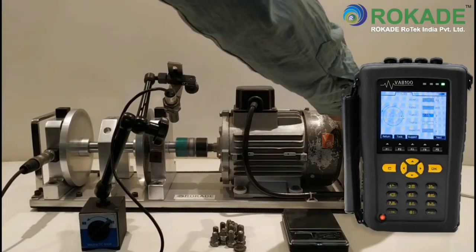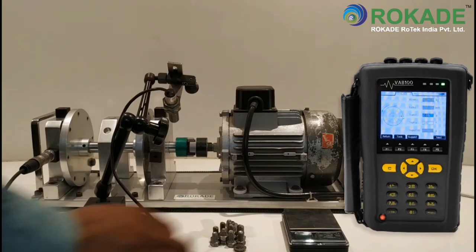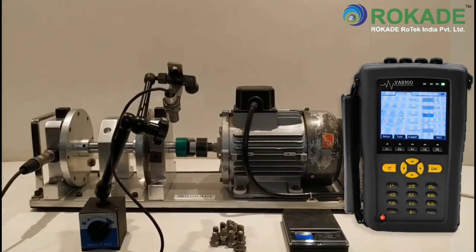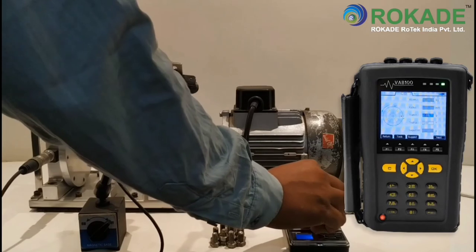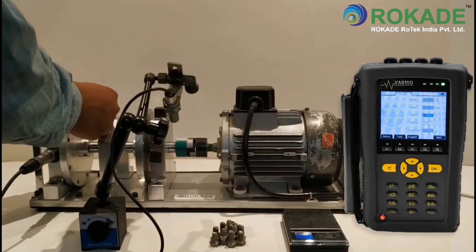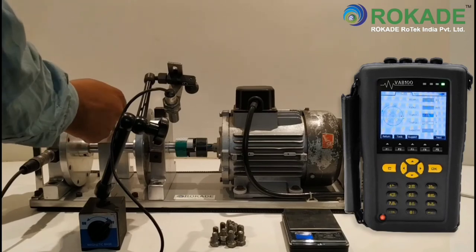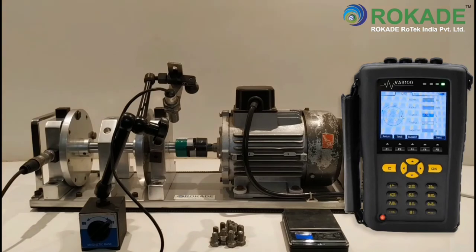Stop the machine. Now add a trial weight. Enter the trial weight in grams, and consider the trial weight angle as zero degree. After that click on next.